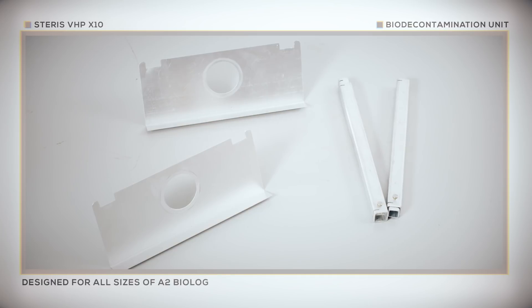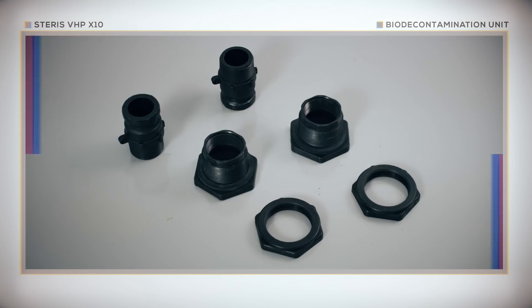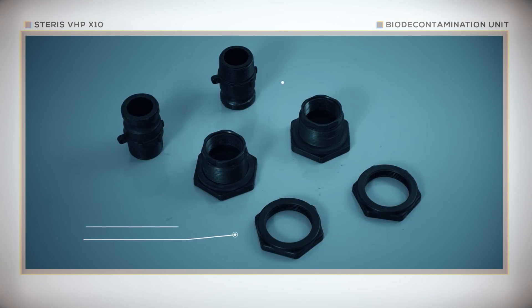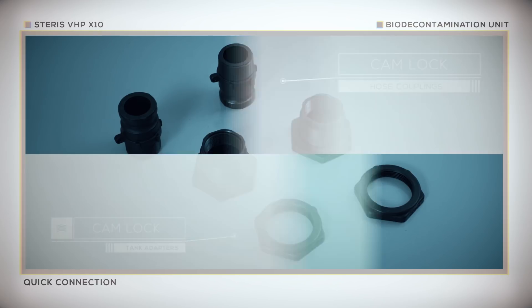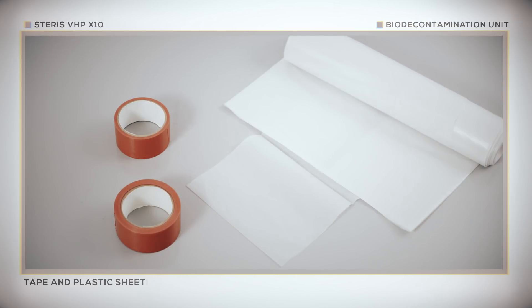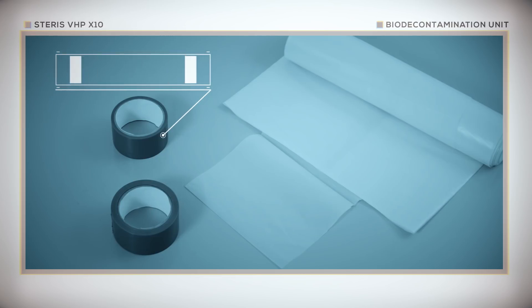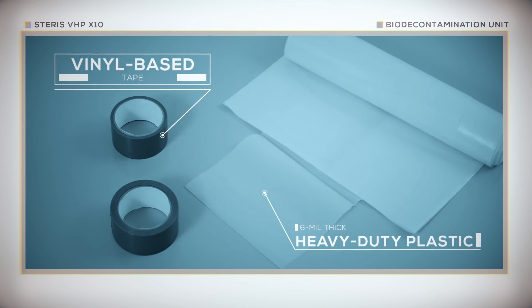Designed for use on all sizes of A2 biological safety cabinets, the sash adapter and return frame can be adjusted for easy installation. Additionally, there are two CamLock tank adapters and two CamLock hose couplings which allow for a quick connection between the X10 unit and cabinet. Tape and plastic sheeting are also required to seal the biosafety cabinet before bio-decontamination. These items are not provided by Steris but are readily available from hardware or home improvement retailers. Steris recommends a vinyl-based tape that leaves minimal residue behind on surfaces, and 6-mil thick heavy-duty plastic sheeting.